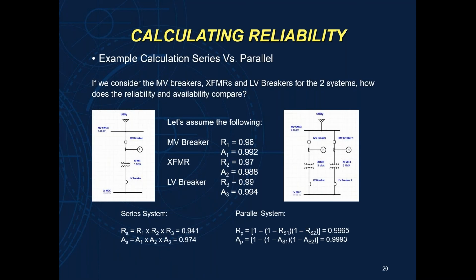So here's series versus parallel. For the purposes of this calculation, we're going to ignore the medium voltage switchgear and the low voltage MCC. Let's just ignore those components and focus solely on the feeder, the transformers and the breakers. For the series system, given these arbitrary values I put in here for reliability and availability, as you can see on the left, the series system, the reliability is 94.1% and the availability is 97.4%. The parallel system, as you would expect to be much higher, is 99.65% and 99.93%.